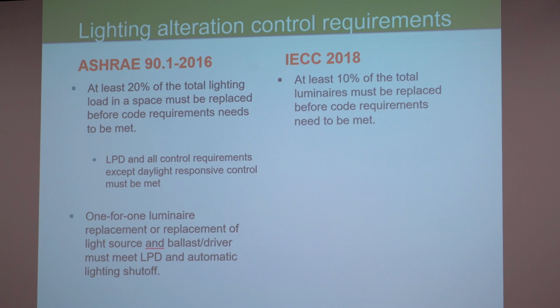Unless the lighting alteration is what they call a one-for-one alteration. That's where you literally swap one fixture for another fixture. Or you replace ballasts and drivers and the light source in each existing fixture. If you do that, then you only have to comply with automatic shutoff and the LPD, or lighting power density, watts per square foot. IECC 2018 has gotten even more stringent, and they basically say now if you change 10% of the luminaires in a space, and it's not lighting load, it's number of luminaires, you're supposed to meet all the new construction requirements for that space.